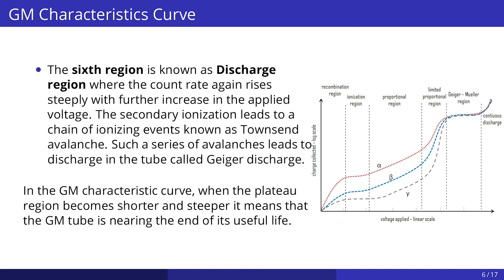In the GM characteristic curve, when the plateau region becomes shorter and steeper, it means that the GM tube is nearing the end of its useful life.